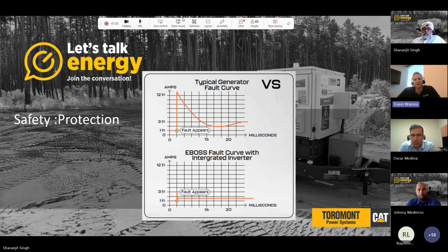The other one that's really interesting is because this is a DC coupled system, like we talked about before, the load is only coming off of the battery. So the generator then just charges the battery through the DC bus inside of the system. What this really means is the inverter is what's powering the load. When the load is only powered off of the inverter, now that inverter can control what we call, I'm sure everybody's familiar with the NFPA 70E arc flash rating. And with standard diesel generators, they have a fairly high arc flash protection boundary where you exceed the 1.2 cal per centimeter squared. I'll get really into the weeds here with that incident energy of a standard generator. But because we have an inverter that drives the output, the inverter detects, at basically a millisecond level, a short in the output system.